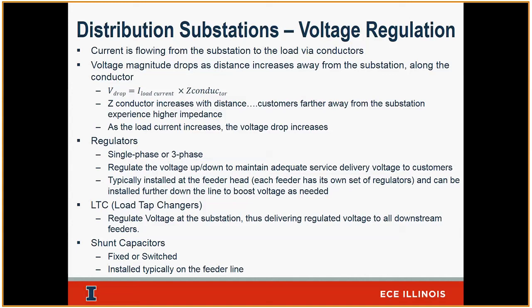That helps us a ton. What turns out is that 125 is not very efficient, because it could cause high power losses. It also could cause inefficient use of energy inside your home. Some appliances might consume more energy at 125 than they would at 120. So there's a huge initiative in Illinois to figure out how to optimize the voltage for every feeder, so that you're still within the band but making energy delivery efficient. You're minimizing the losses and the usage of energy while still delivering energy within this band. Today, at Ameren, we have about 2,600 feeders. Of these, about a third, so about 1,000 circuits, are going to have brand new controls, brand new mechanisms to optimize the voltage, to deliver more savings to our customers in terms of energy and optimize the energy consumption.